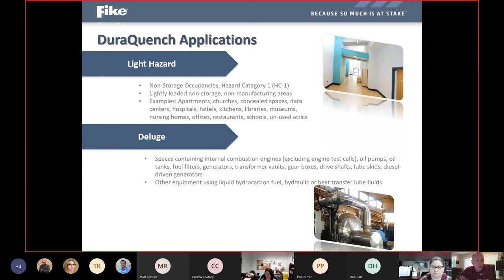Surfaces and floors are always going to get wet anytime you're dealing with water. But with a mist system, they're going to be wet but not saturated, and you'll be able to clean up with basically a towel or a light mop, versus buckets and squeegees because of the sheer amount of water you would have with the flooding factor of a sprinkler system.